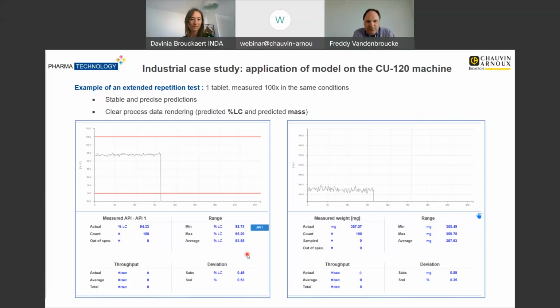The machine displays the mass measurements and the measurements of the fraction ratio. This is the ratio between the fraction of the formulation that is in the tablet and the fraction of the nominal formulation. We can see that the measurements are repeated quite precisely, and the standard deviation of the fraction ratio is below half of the RMSEP that we got and have seen on the previous slide. The standard deviation of the mass measurement is below 1 milligram.